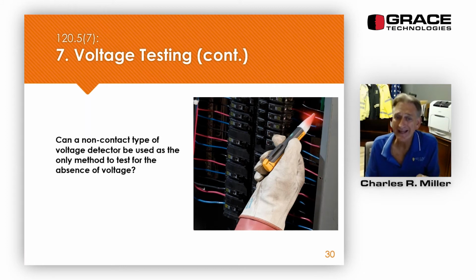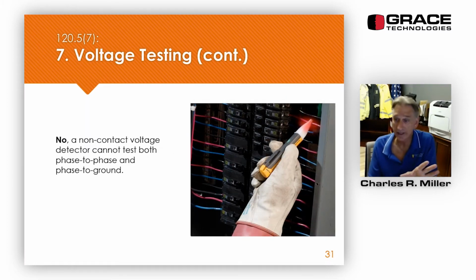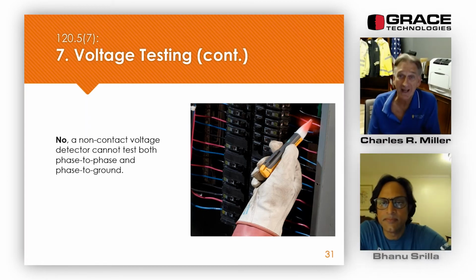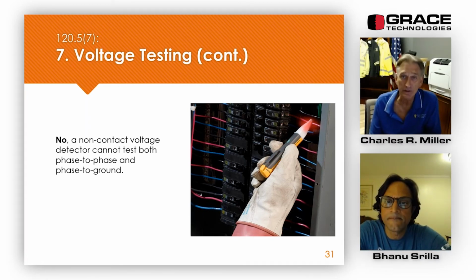Can we use a non-contact type of voltage detector as the only method to test for the absence of voltage? And the answer is no. I'm sure you were shaking your head as well. How are we supposed to test for the absence of voltage? Well, with a voltage stick like this, a non-contact, you could test it on something live before and after testing, but this cannot test phase to phase and phase to ground. So it cannot be used as the only method. Can it be used as a first line of defense? I don't have a problem with that.